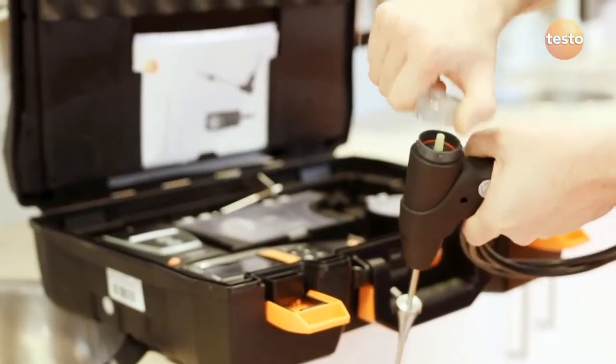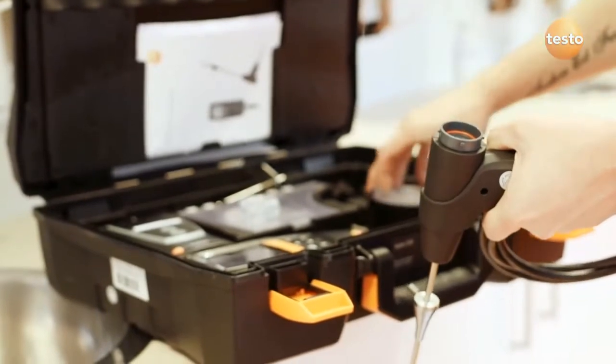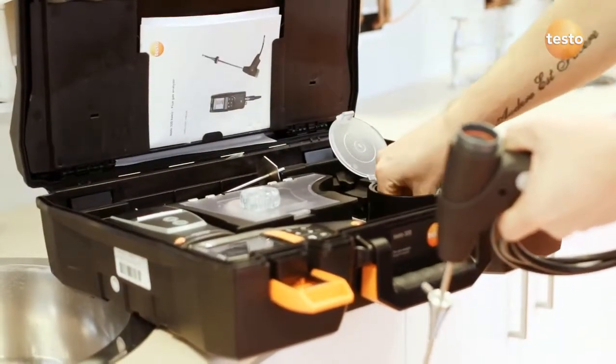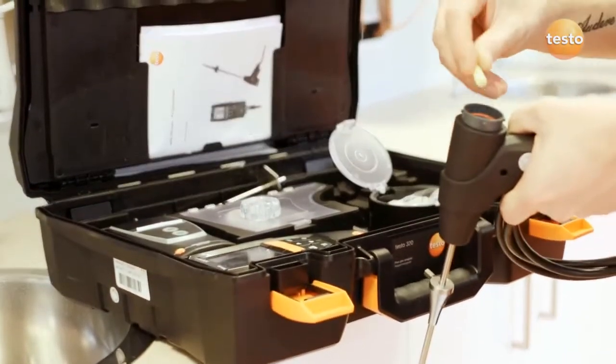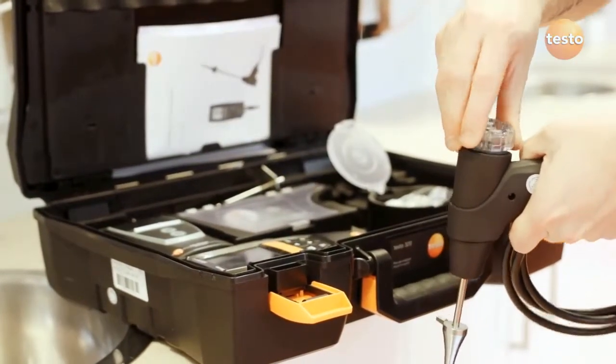Regularly check the filter in the probe handle, which is really easy to do on any Testo analyser. If the filter's dirty, throw it away for a new one. If it's wet but clean, you can fit a dry one and keep the old one to dry out.